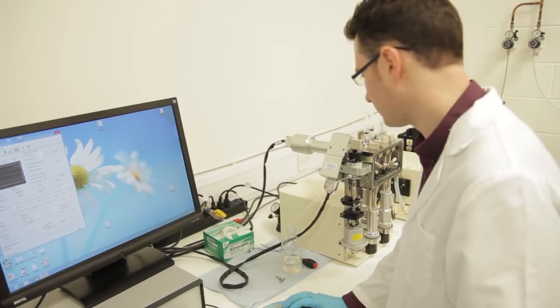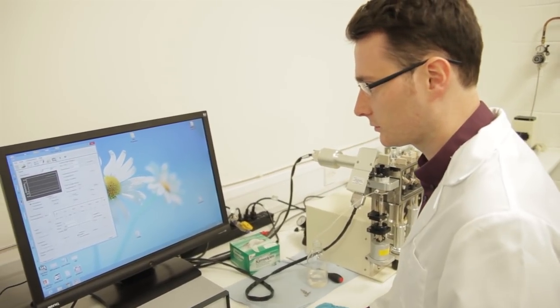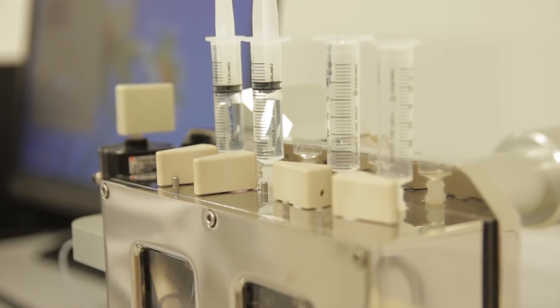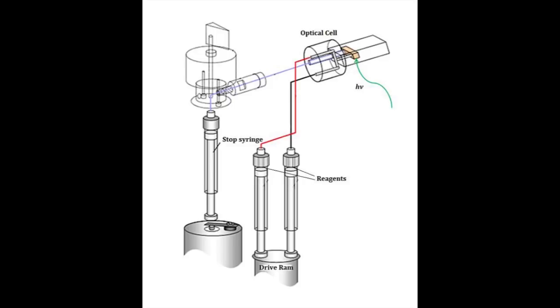The principle of operation is relatively simple. Two reagents are contained within two syringes which are then rapidly mixed together using a pneumatic drive ram. The resulting mixture is pushed through an optical cell which displaces the old contents into a stop syringe. This causes the flow to stop and for data acquisition to commence.